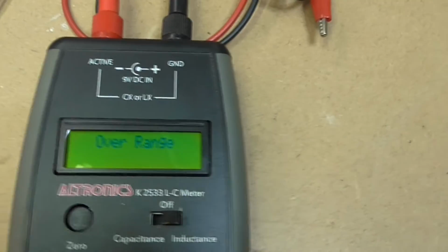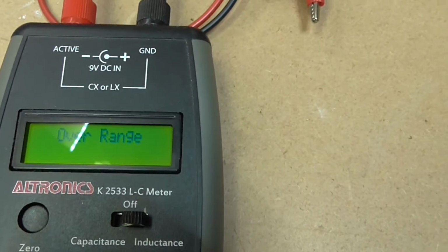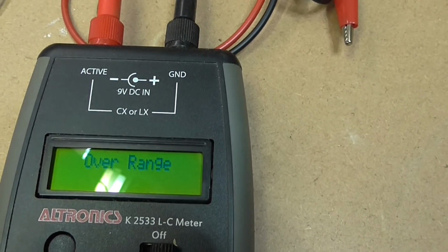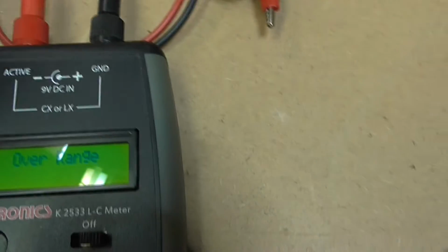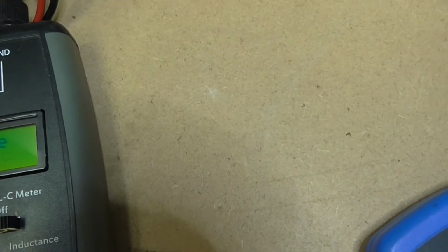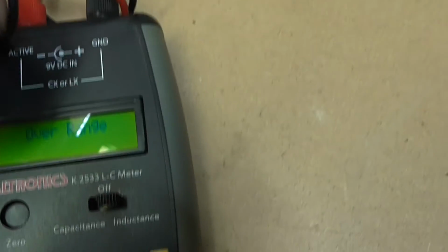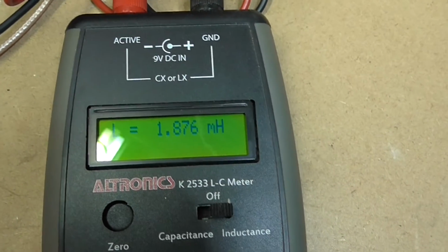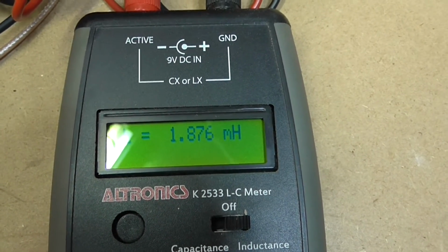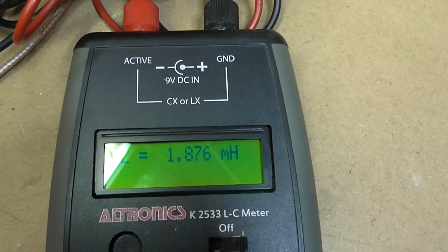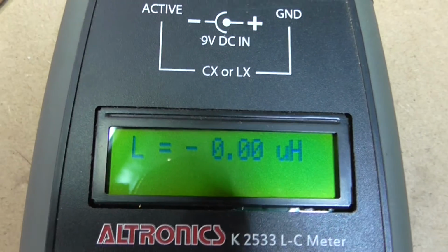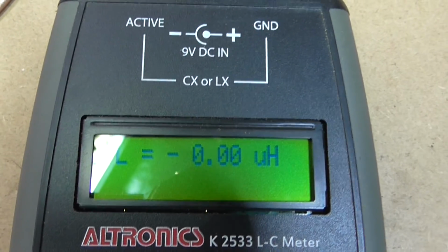First we turn it on to the inductance setting. It does a calibration, and it's not happy because it needs to be reading something. So I'll short the two output terminals and push the calibrate button, then try again. Now with the leads shorted and the calibrate button pressed, we've got basically 0 on the display.